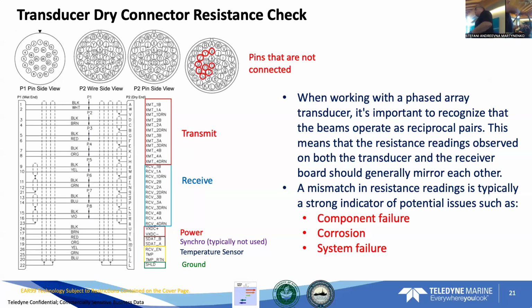Got it. Now, one thing that's important about this cable is we can only replace one portion of it. We can only replace the dry side. We cannot replace the wet end side of this cable. So if it gets cut or nicked or anything, it can flood the actual transducer and flood the cable. So it's important to know that we cannot replace this part. If this is damaged, we have to replace the entire cable.